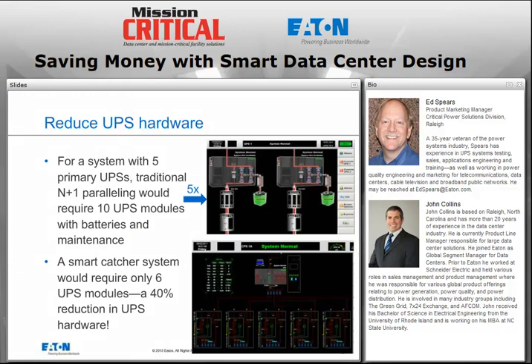And as we said before, we talked about a little bit towards the beginning of the presentation, it allows me to reduce the UPS hardware that I have to deploy. For example, if I want an N+1 redundant system at, let's say, 500 kW, then that would mean traditionally that I buy two 500 kilowatt UPSs, and each one might have, let's say, 4 refrigerator-sized battery cabinets that weigh 5,000 pounds each. So that's 8 battery cabinets, 2 UPSs. I'll need switchgear to tie them together in parallel. And I need to think about floor space and upfront cost and maintenance for the batteries and maintenance for the 2 UPSs.